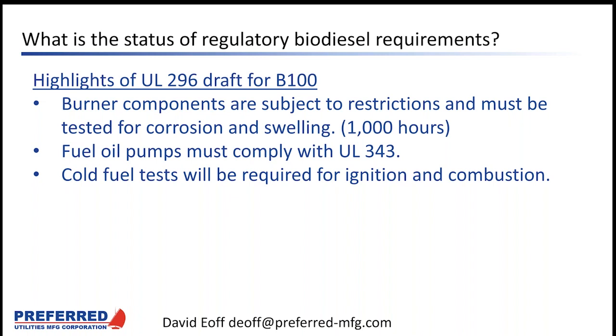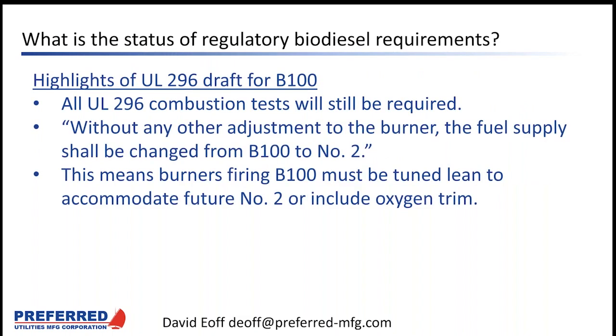Fuel oil pumps must comply with UL 343. So this continues to mean that submersible pumps will not be allowed within New York City. I think City of Chicago is also the same. Their pump sets on boilers have to be UL 343. Cold fuel tests will be required for ignition and combustion. Biodiesel has a higher cloud point than diesel, so it needs to be tested at cold conditions to make sure the burners can light off and burn cleanly. All of the normal UL 296 combustion tests will still be required.